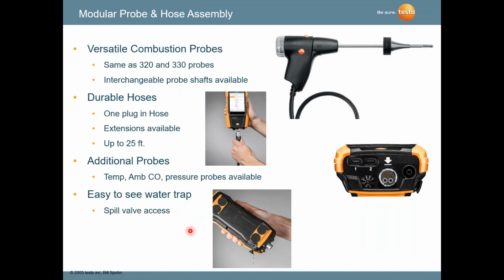Probe and hose assemblies we talked about. Plug-in hose extensions: in some of our instruments, you can go up to 25 feet. Hose extension, ambient CO, you can attach other probes to it. Our water trap is on the bottom of the instrument, and you can visually see the level of water, and there's a spill valve here. You open that spill valve and dump all the water out. You want to do that after the test. There are fill lines on here, so if you're holding the instrument upright and you surpass a fill line, it's time to dump that water out, because you don't want to pull water into an analyzer.